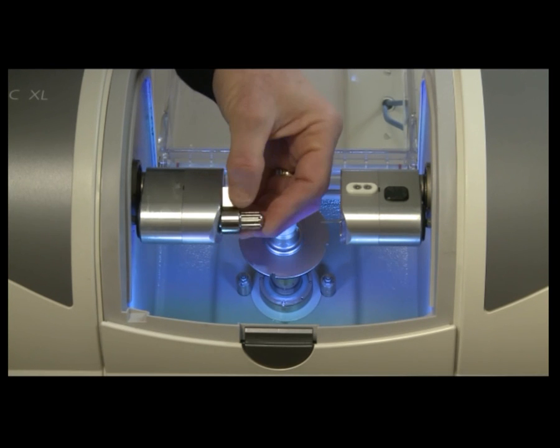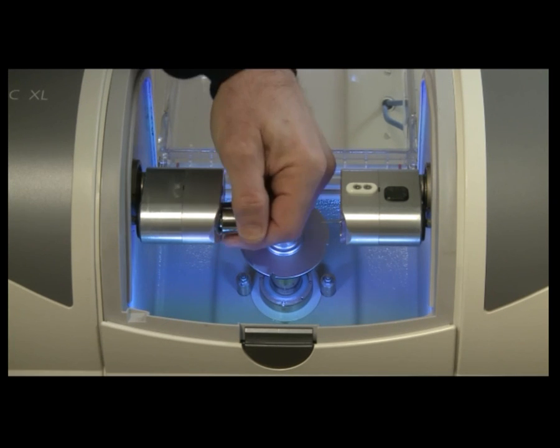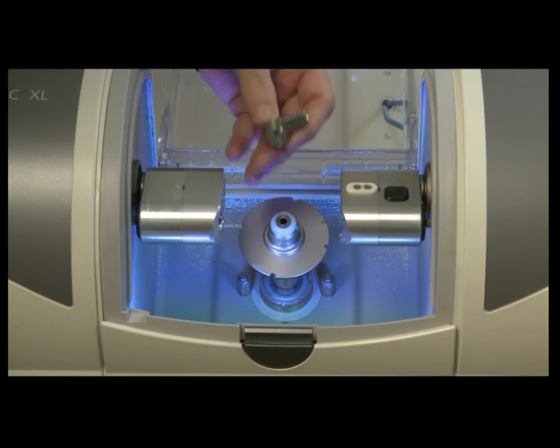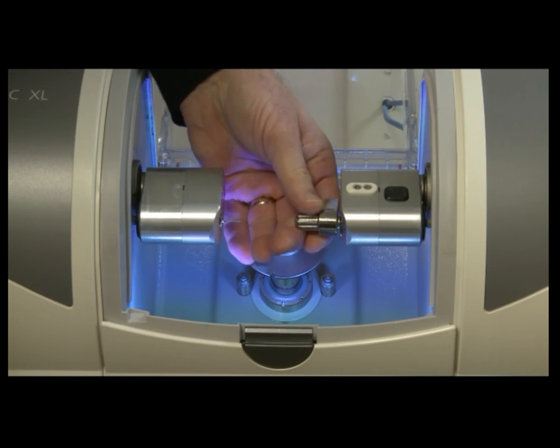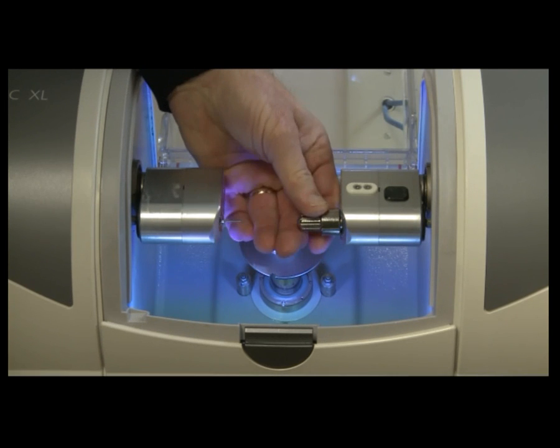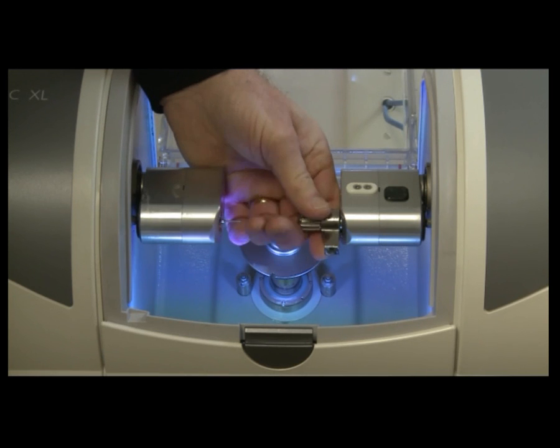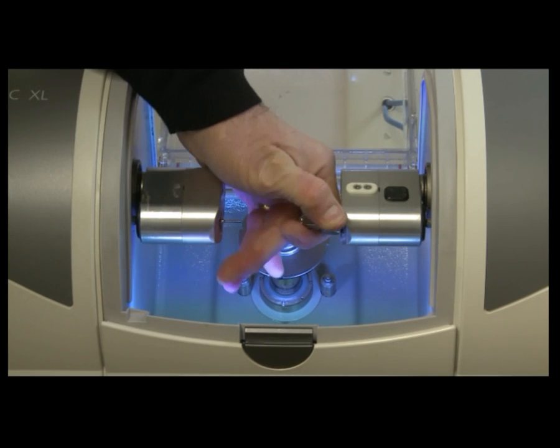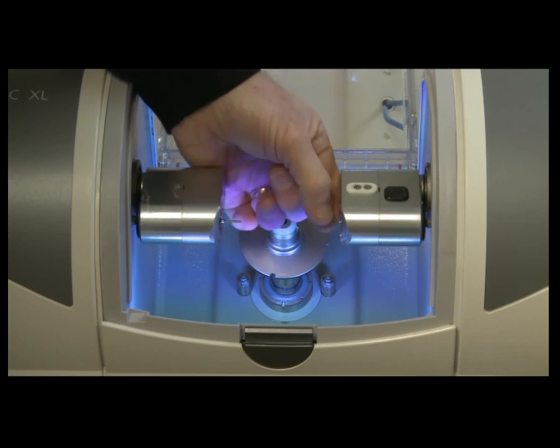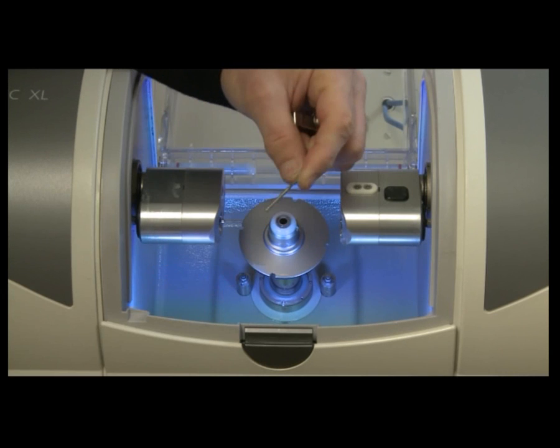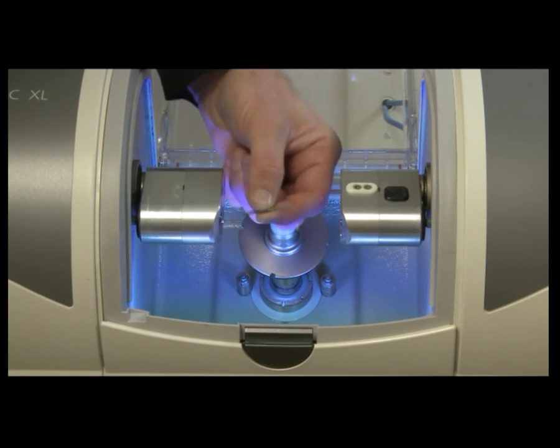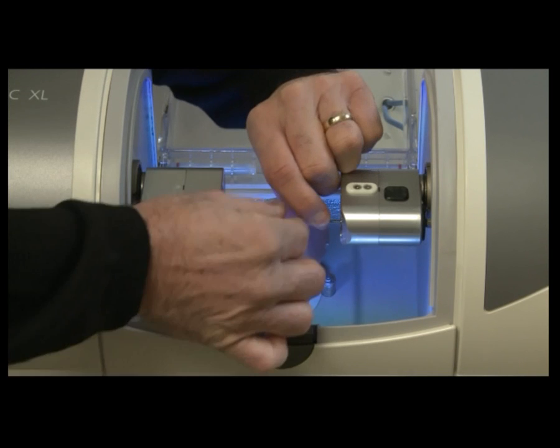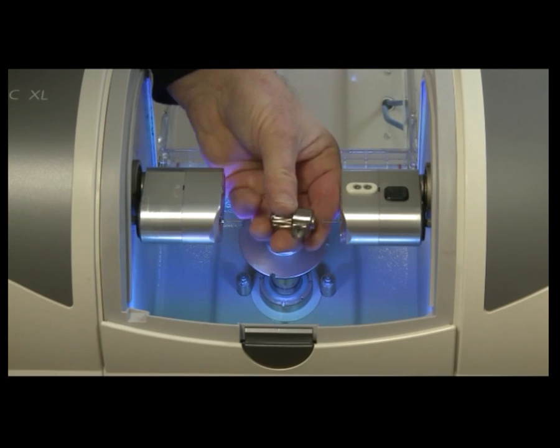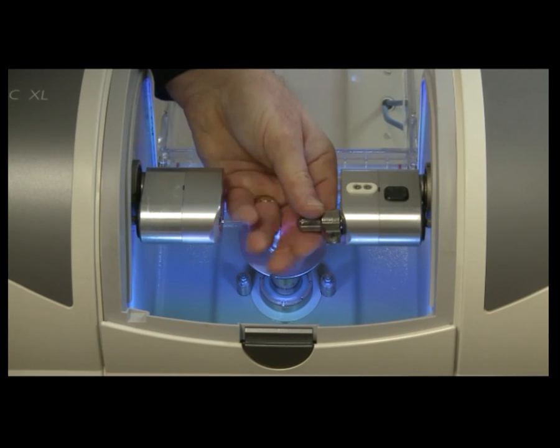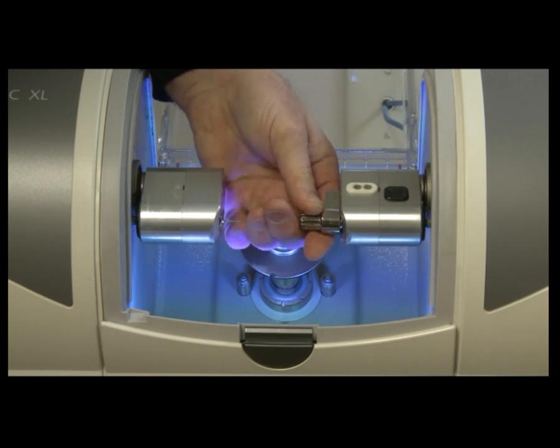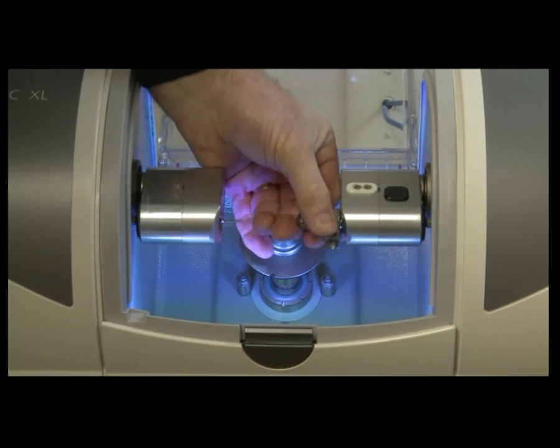I'm going to turn this to the right and again screw it in until it clicks. It's a torque wrench, so you can't over tighten it. And you do the same thing to the left side. Remember to take it totally out, take out the chuck, and then replace it. The next step, we're going to put in our calibration specimen in the middle, and it looks like an arrow. On yours, you're going to have to remove the center section of your chuck. In order to do that, you're going to take your hex wrench, which is your Torx wrench, just like you're going to be putting in a block, loosen it up, and then in the center section of your chuck, take it and remove that whole center section.